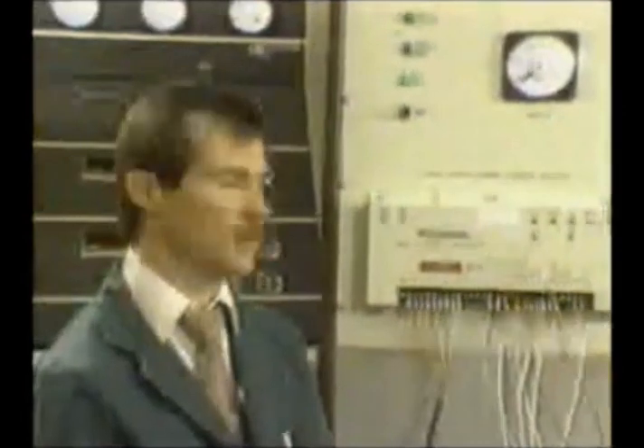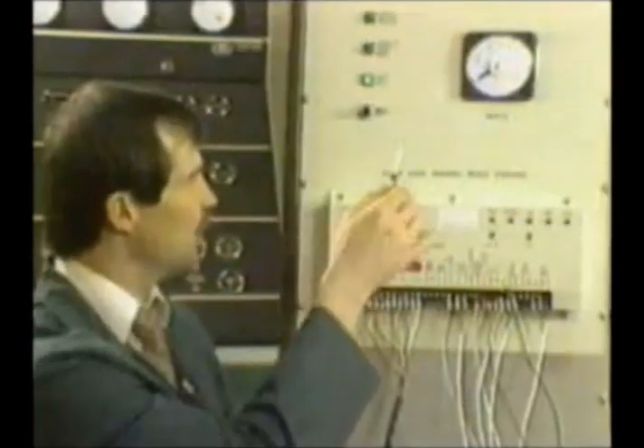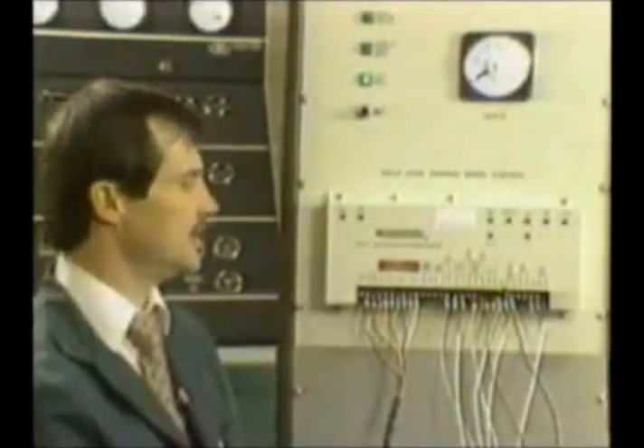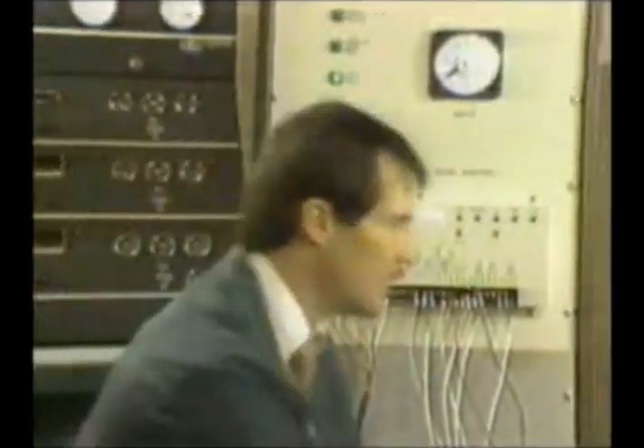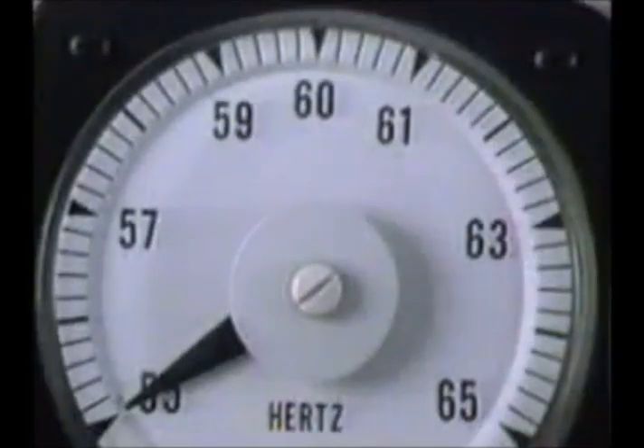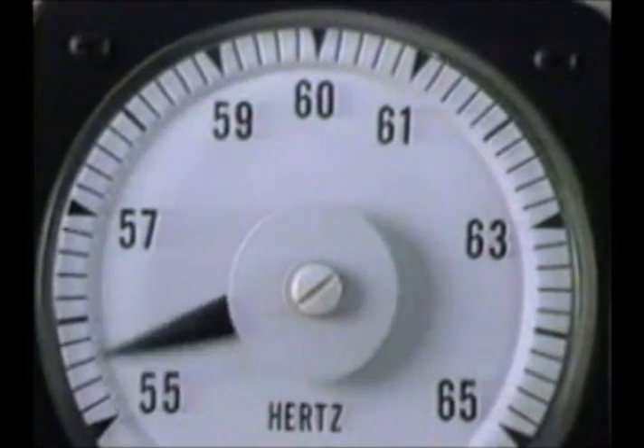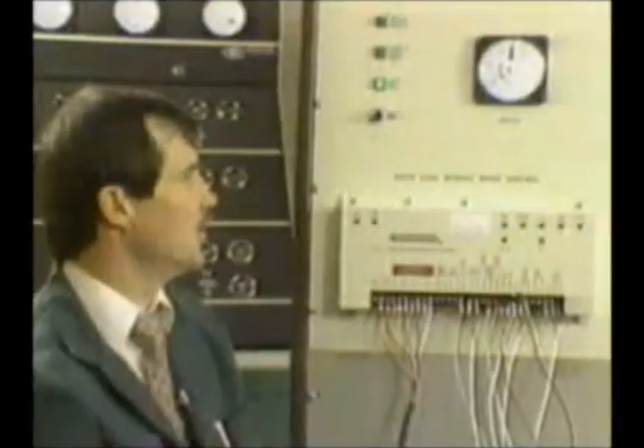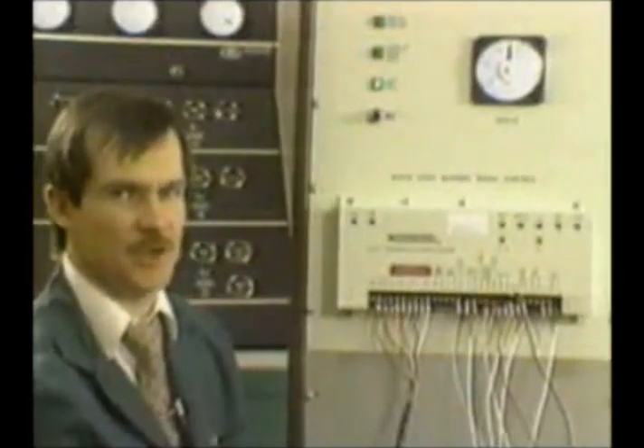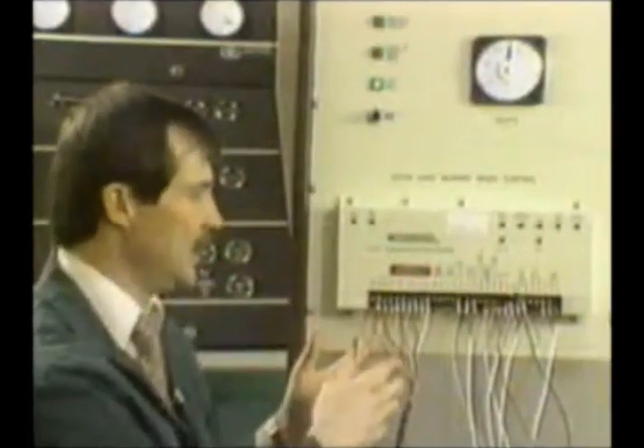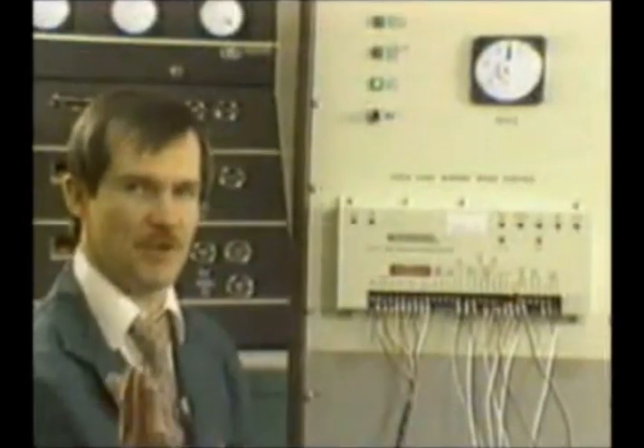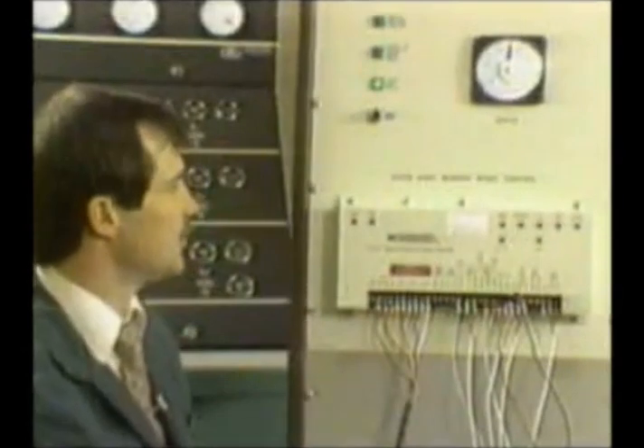And you'll see with this start fuel limiter in, we're calling for less fuel, saving you fuel, and then your emissions will be a lot less. And we'll start up smoothly and come right into 60 hertz. Let me go ahead and start it. And the unit comes right up and controls at 60 hertz. It makes it easier for our control to keep from overshooting 60 hertz because it's not getting all that extra fuel early. So that's the start fuel limit.